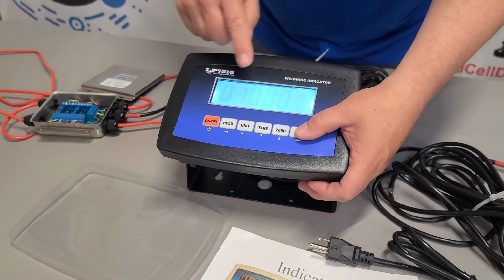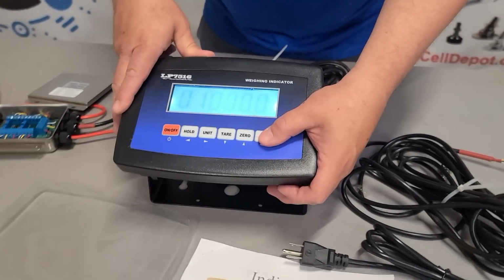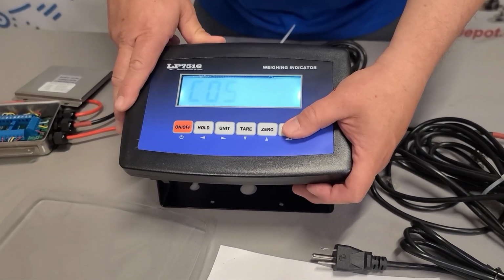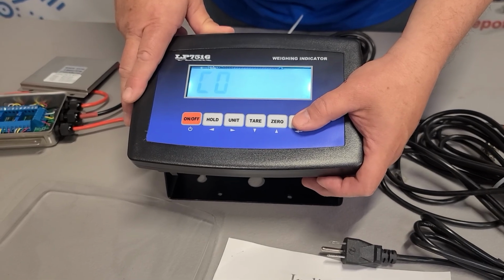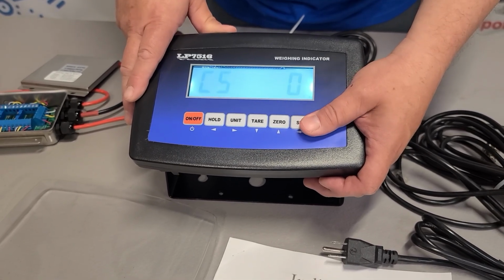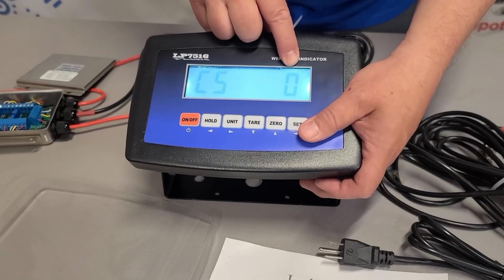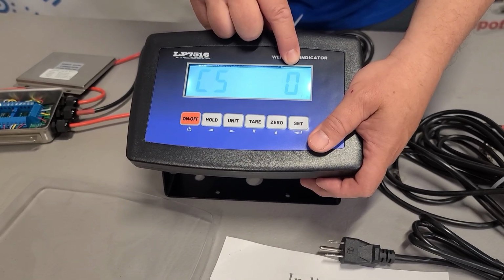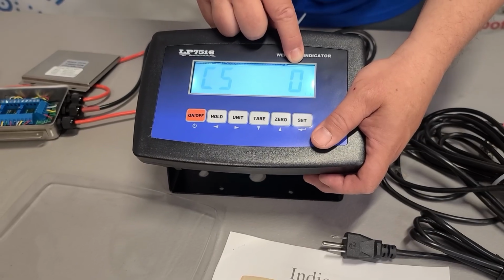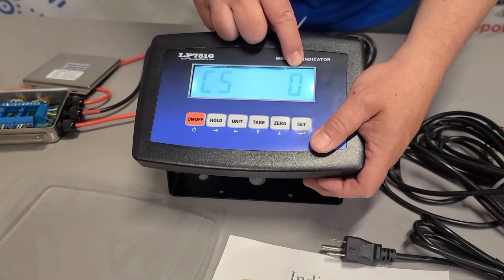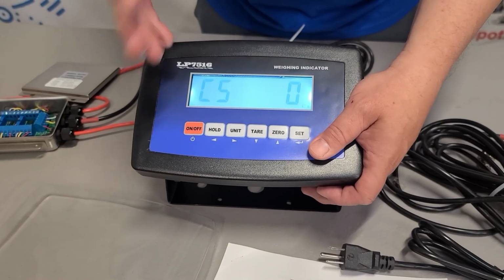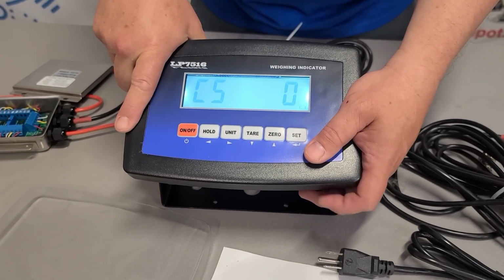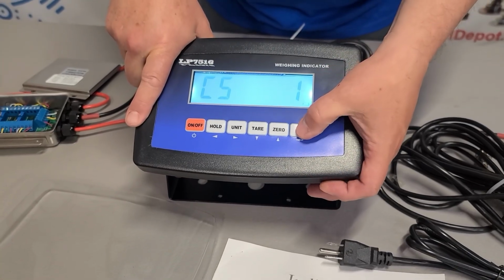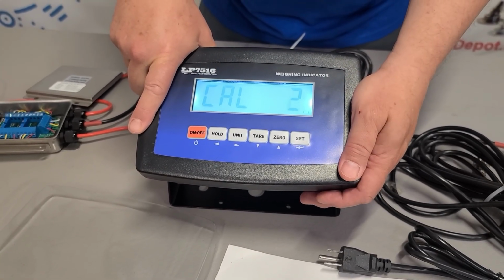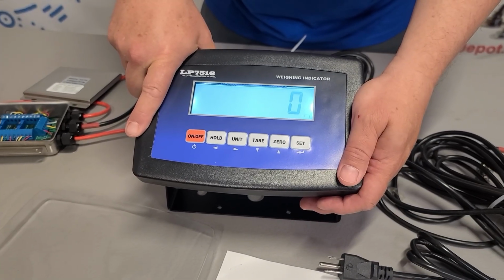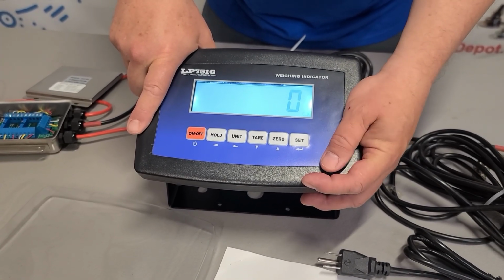So we leave it at 10,000, but if you need to change it, there are the arrows and you change the numbers. Now, C5 is going to be your 0 calibration. And don't forget, make sure nothing's on the platform at this point. It's going to tell you 0 at this side after you press set, because it's asking you if you want to have a 0 calibration or not. Are we having a new 0, or are we using the old 0, whatever this indicator was tested with. Now, we're going to use a new 0. So we're going to increase that to 1, and we're going to hit set. It's going to count down to take the new information from the scale base. Now it knows where the new 0 is.